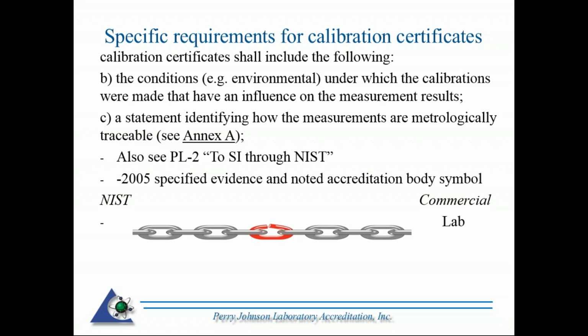Any conditions under which the calibrations were made that have an influence on the measured results: temperature, humidity, barometric pressure. A statement identifying how the measurements are metrologically traceable. One of the annexes in the 2017 is Annex A, which is in regards to traceability. Also see PL2. When you reference traceability, a lot of people in the US like to see NIST. That's inappropriate. If you're going to reference NIST and traceability, the verbiage is you're traceable to the SI, that's the SI unit actually, through NIST. So it cannot state being traceable to NIST, it's always through NIST.